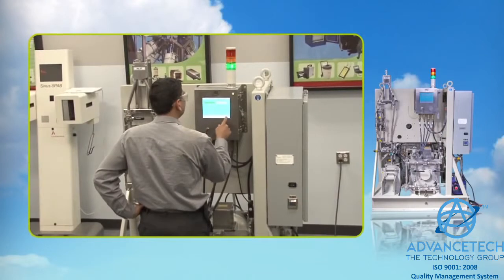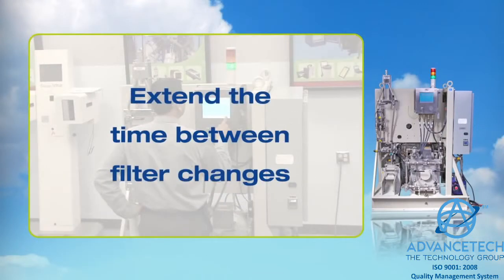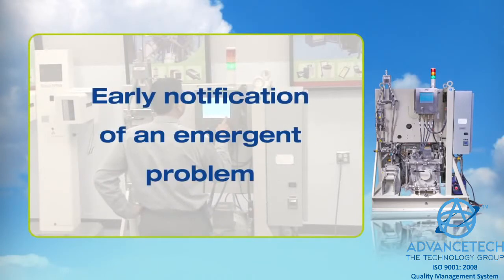First, it may be possible to extend the time between filter changes by responding to an indication of the state of the filter rather than to a scheduled filter change interval. It also provides early notification of an emergent problem that could lead to a filter replacement in advance of the next scheduled activity.